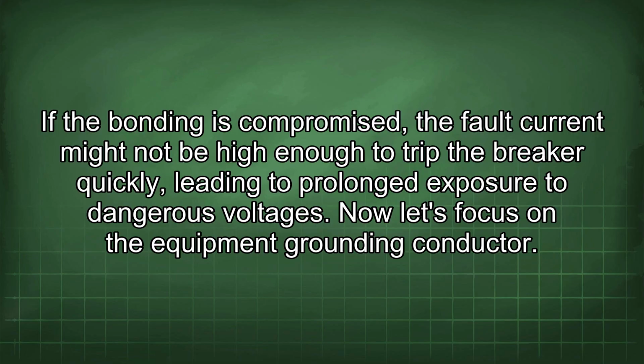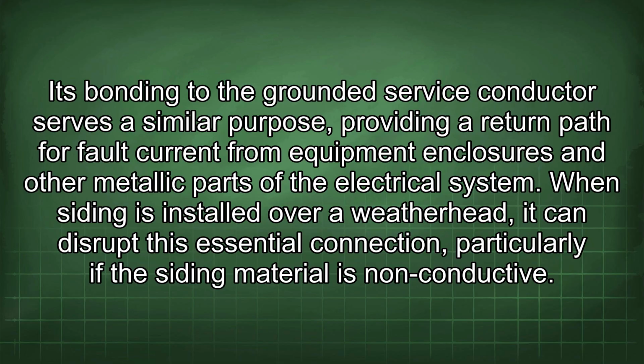If the bonding is compromised, the fault current might not be high enough to trip the breaker quickly, leading to prolonged exposure to dangerous voltages. Now let's focus on the equipment grounding conductor. Its bonding to the grounded service conductor serves a similar purpose, providing a return path for fault current from equipment enclosures and other metallic parts of the electrical system.